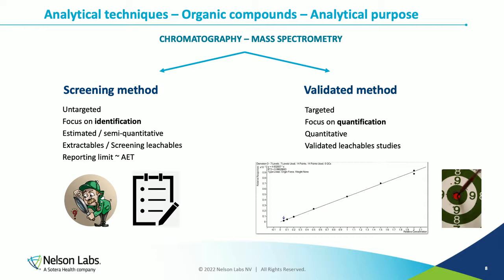Whatever technique is used, it can be applied in two ways: as a screening method or as a validated method. When used as a screening method, the purpose is an untargeted analysis — you want to discover all your extractables and leachables, focusing on identification. You can also quantify to some extent, but it is not fully quantitative — rather estimated or semi-quantitative. This approach is typically used for a screening study.